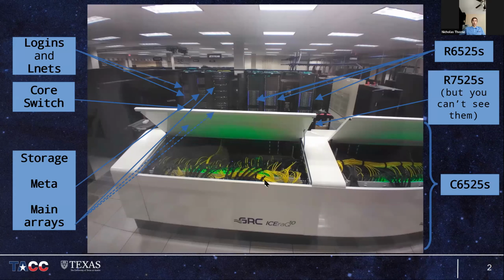There's a little space for switches across the front. Typically, GRC's other customers don't see the level of switches because most of their customers aren't running a high-speed fabric. For the high-speed fabric, you're not supposed to put fiber cables into the mineral oil because it degrades the wrappers around the fiber a little bit faster, and they can become very fragile over time. So we're obliged to stick to copper cables. The copper cables for HDR are really thick. And so getting all of that stashed in this little space over here, plus this space over here, well, if I open these panels up, you would see it's very tight.